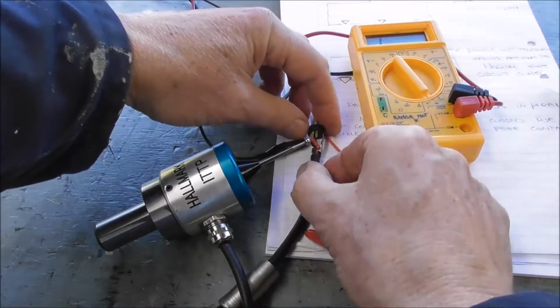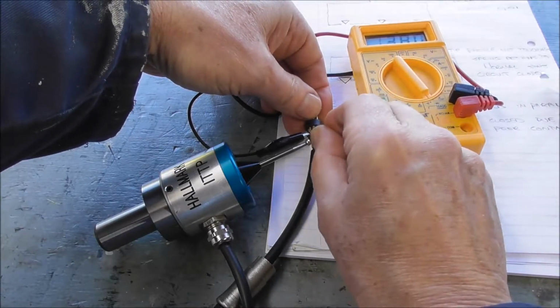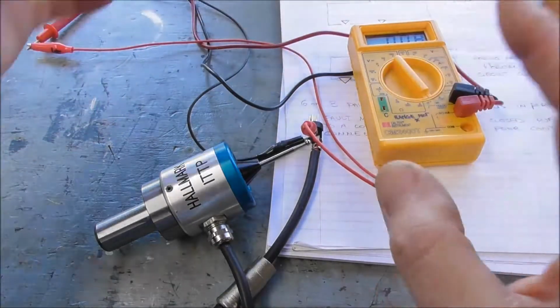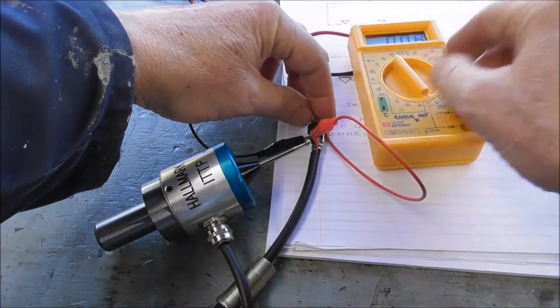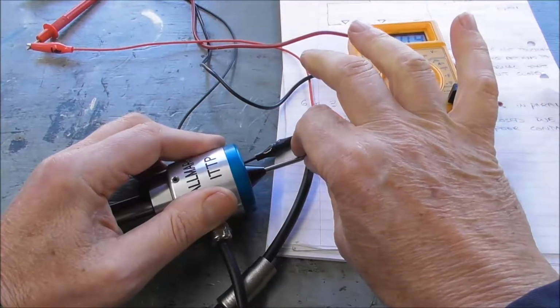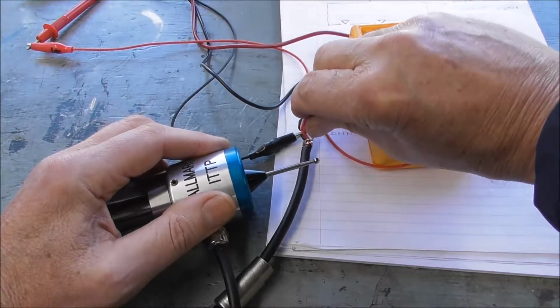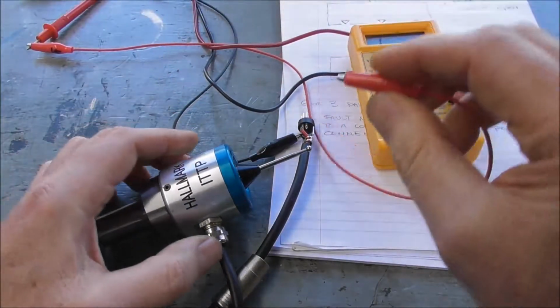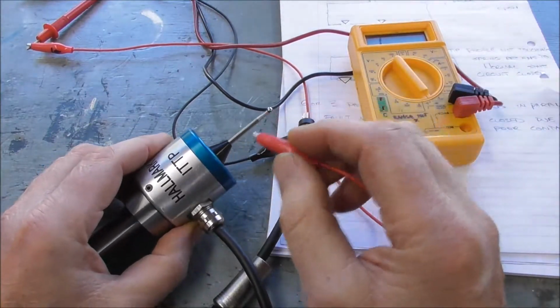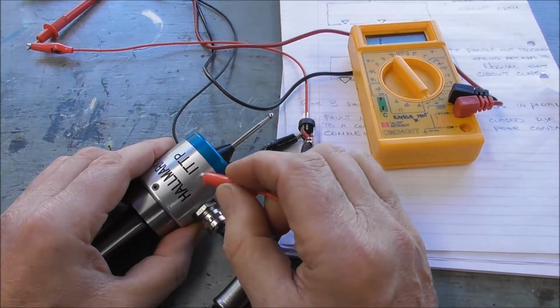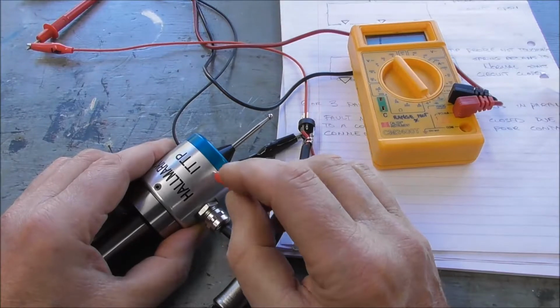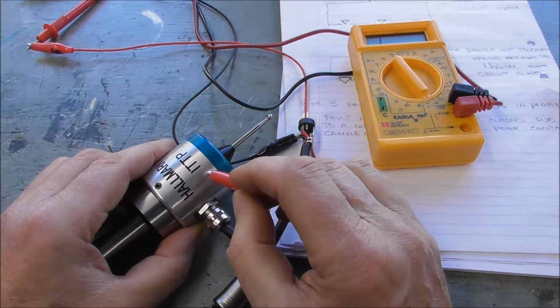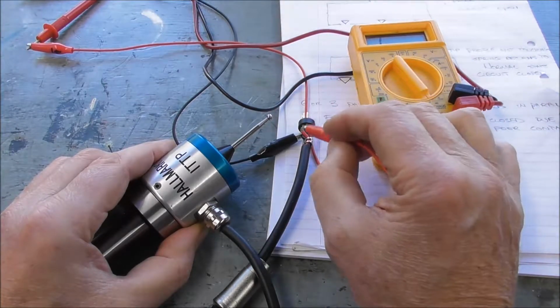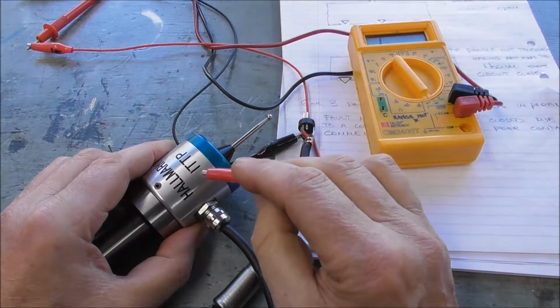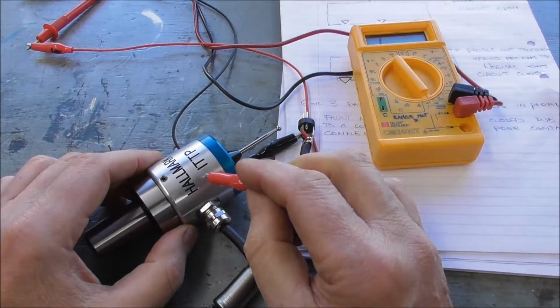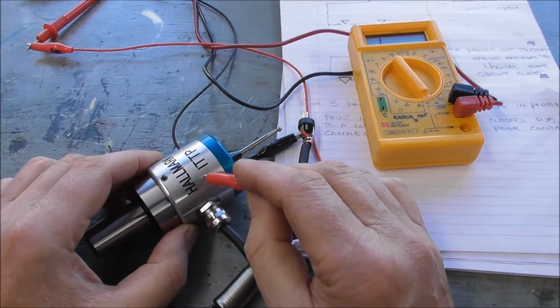Okay, so to test for a short, we've got our little alligator clips set up here on the DIN plug, like that. And we've got the circuit beeper going. Now if we remove one of those, a bit awkward, the camera in front of me, sorry I'm fumbling a bit here. Okay, now we don't want to have a connection through the body of the probe. And there's nothing there, but if it was beeping, then that would be a sign that there's a connectivity of circuit between the main live wire running through the probe and the body of the probe. And that would be a sure sign of a short, and that would give issues with the function of the probe.